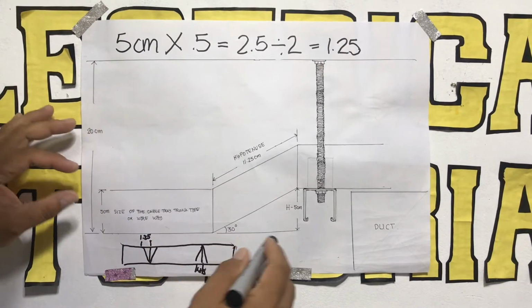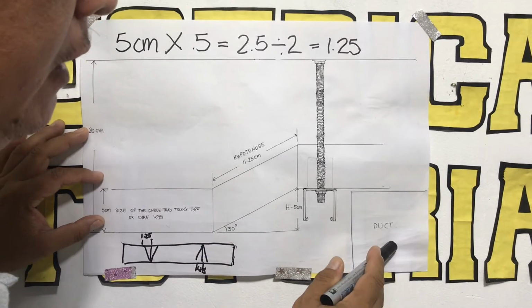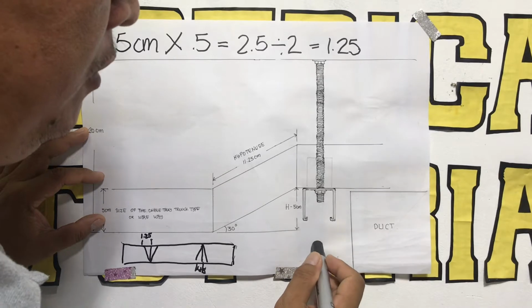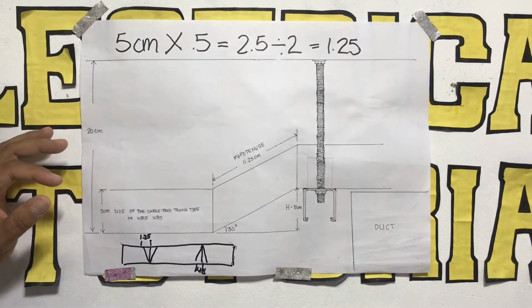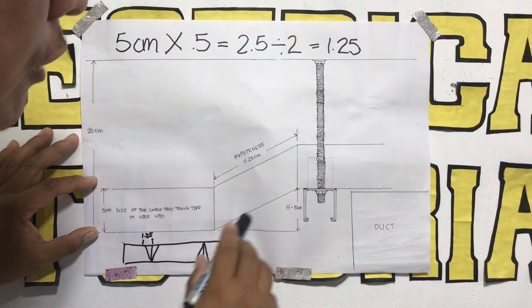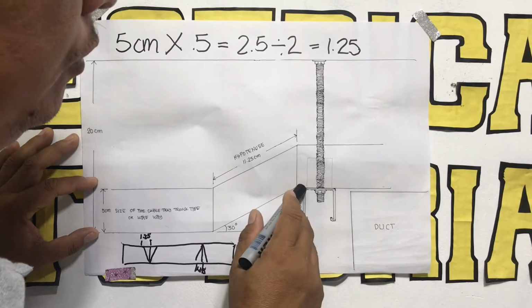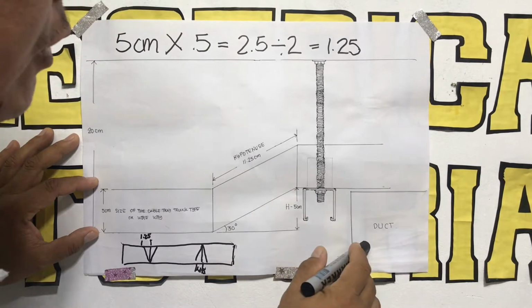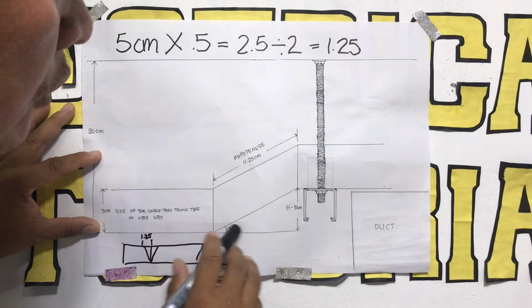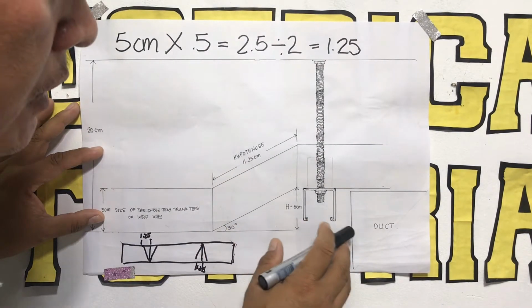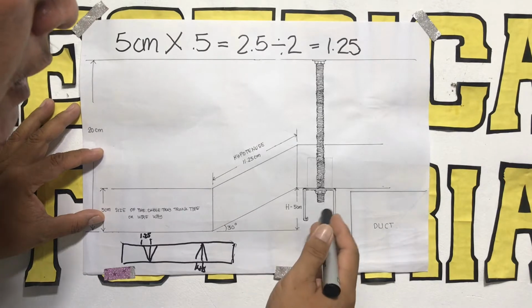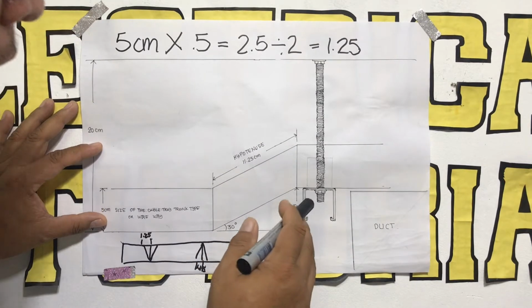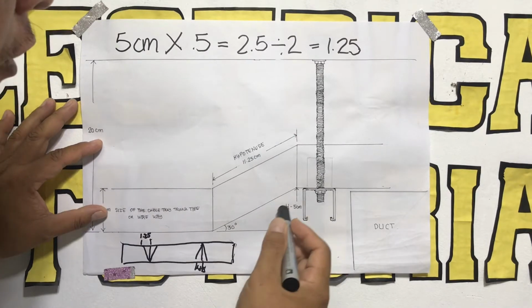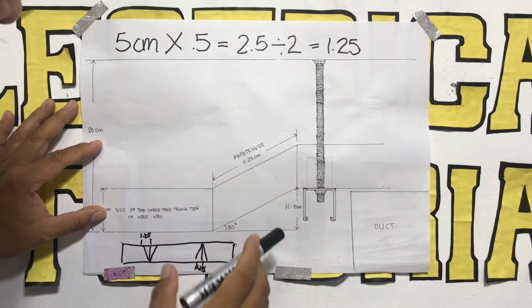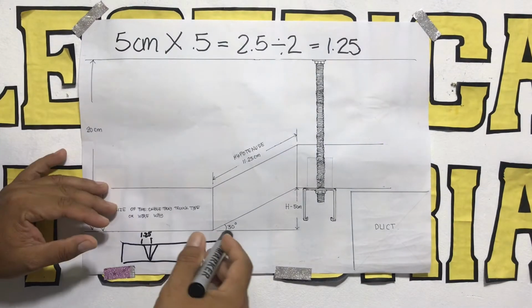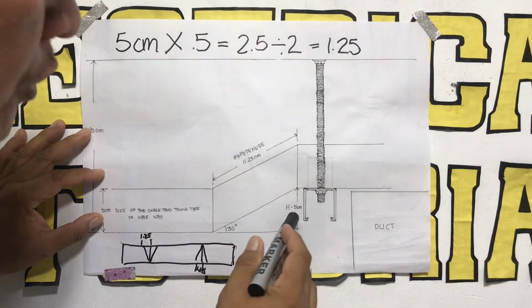Then we encounter an obstruction, for example a duct, fire protection pipe, or PVC. We need to take off to escape or pass by that obstruction. In this illustration, to escape the duct, fire protection pipe, or PVC, we need 5 centimeters, because we only need a short takeoff and we're going to use 30 degrees to get the hypotenuse of the takeoff.